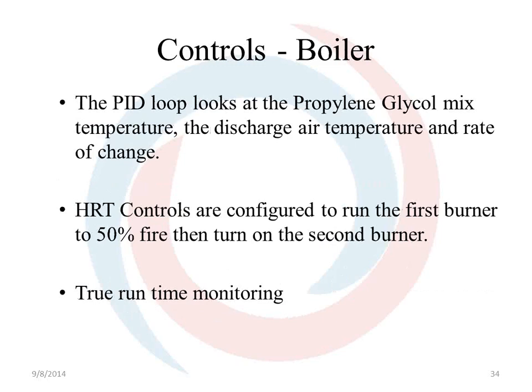A little bit about the controls on the boiler. The boiler is controlled by this proportional integral derivative. By looking at the rate of change, it keeps the boiler from making sudden and unnecessary changes. It also helps to prevent the system from overheating the discharge air temperature. When the propylene glycol mix is within this heat band, the boiler modulates to maintain the discharge air temperature. In the event of temperature rises above the heat band, the boiler will stage burners off until the discharge air temperature has fallen below the heat band minimum.